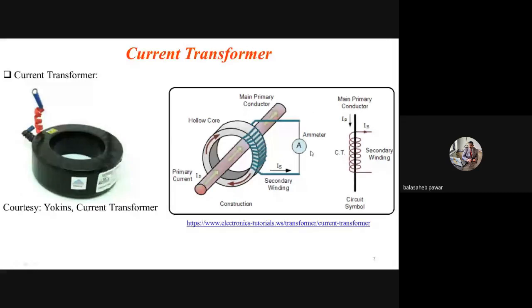For example, see, suppose I connected a 1 ohm resistor across the secondary, right? And I have to measure the voltage drop across that resistor. I can measure it by using a DMM, but that DMM should be on AC measurement, because whatever current flows through the secondary will be RMS current.